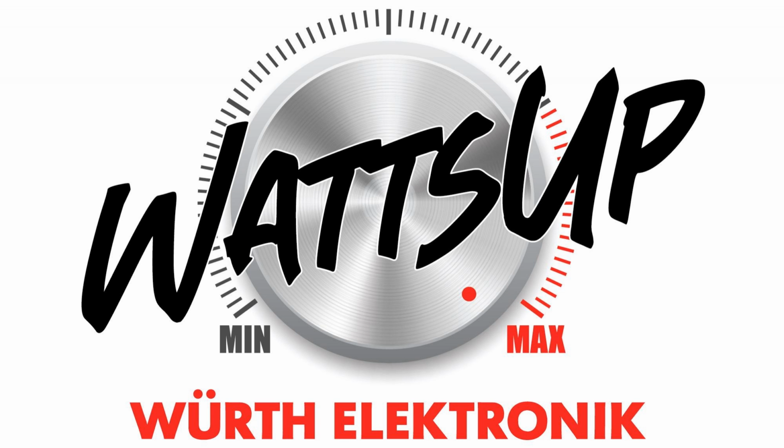Can you describe some of these different types of categories, and why would you choose one type of current sensor over the other? Well, a shunt resistor, these are typically very small and low cost. They also can measure both DC and AC current. The downside to shunt resistors is that they typically have larger power loss in high current applications, and the measured circuit cannot be electrically isolated from the measuring circuit.